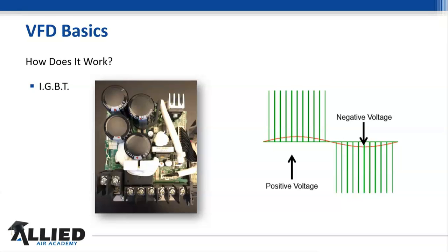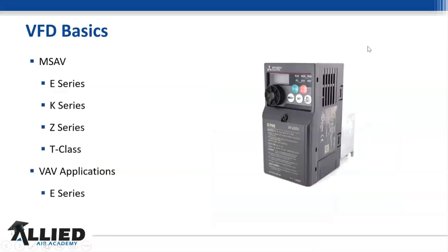But that's what that IGBT is going to do for you, and this is a really good graphic that shows you on there, and you'll notice the timing on the sine wave, how it's going to be affected. So when voltages are really not good, you're going to see this particular wave be affected, and then you may start getting some codes on there, and we don't want to falsely troubleshoot a bad drive and then replace it and put a new drive on there and it does the same thing. It takes a lot to get on the roof and get a unit opened up and work on it. So we definitely want to make sure we don't misdiagnose it.